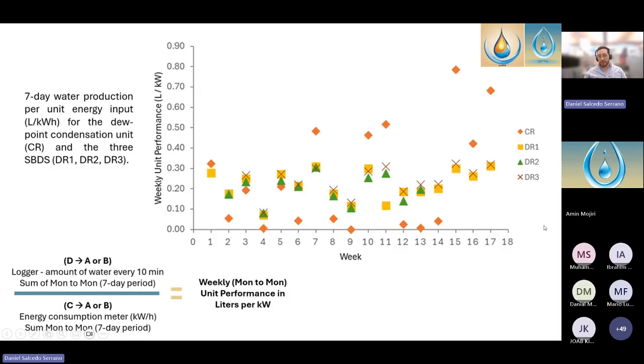And if you're familiar with Arizona or this part of the desert area, there's a phenomenon called monsoon. There's a monsoon season, and all of a sudden the humidity spikes up. But most of the time, due to the low relative humidity, the liters per kilowatt were quite low, and the absorption-based units kept kind of constant, kind of low. I mean, low fluctuations.